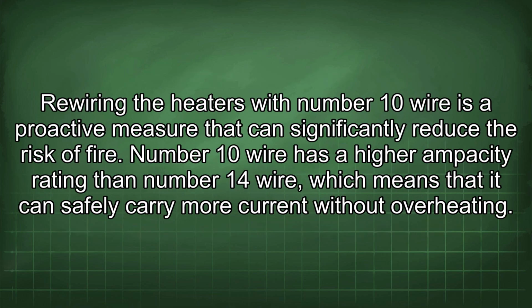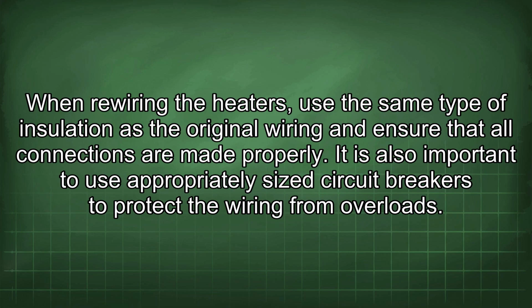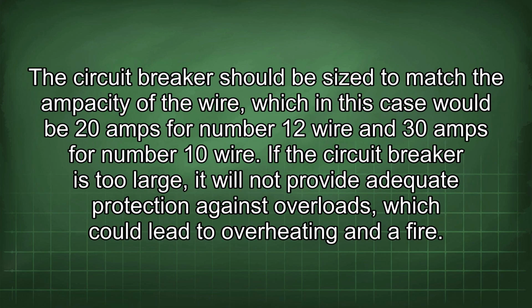Rewiring the heaters with number 10 wire is a proactive measure that can significantly reduce the risk of fire. Number 10 wire has a higher ampacity rating than number 14 wire, which means that it can safely carry more current without overheating. When rewiring the heaters, use the same type of insulation as the original wiring and ensure that all connections are made properly. It is also important to use appropriately sized circuit breakers to protect the wiring from overloads. The circuit breaker should be sized to match the ampacity of the wire, which in this case would be 20 amps for number 12 wire and 30 amps for number 10 wire.